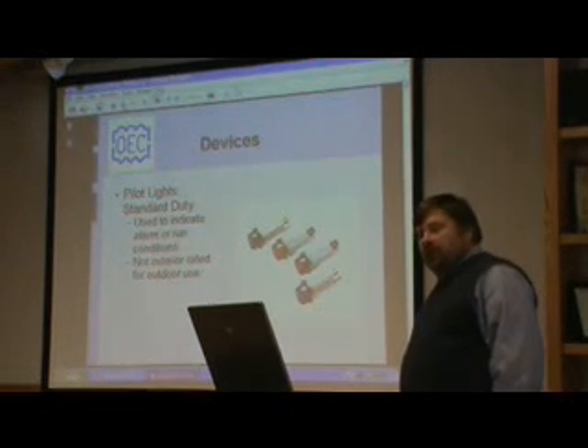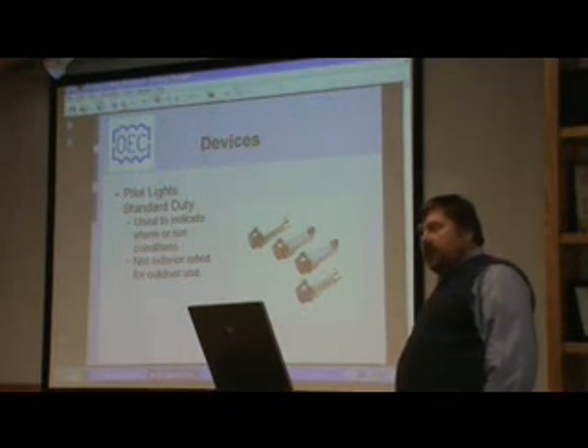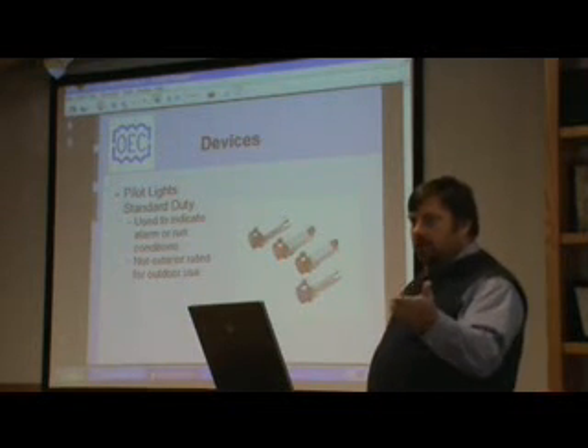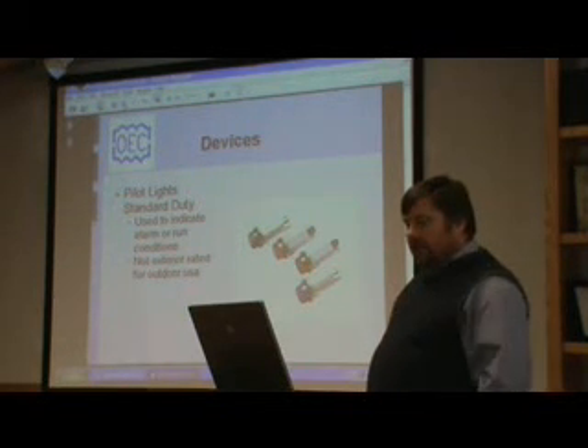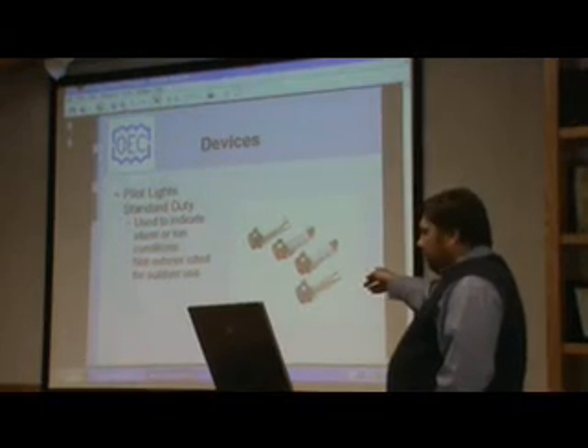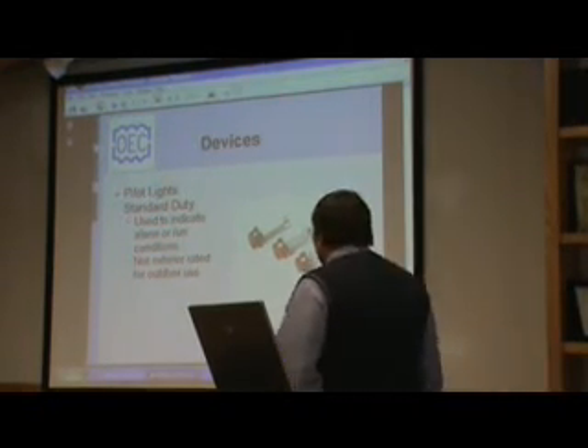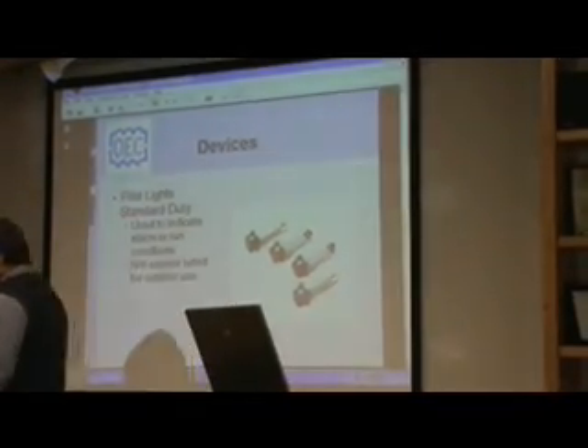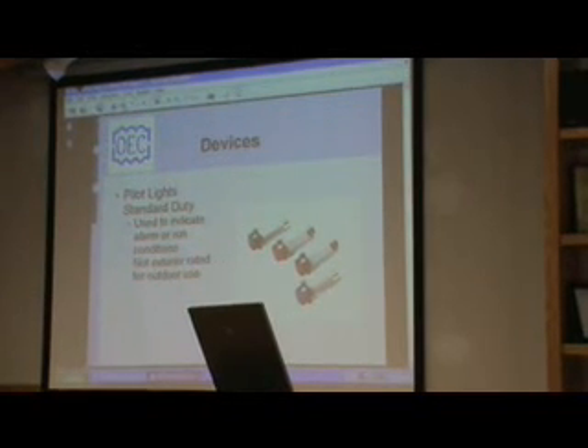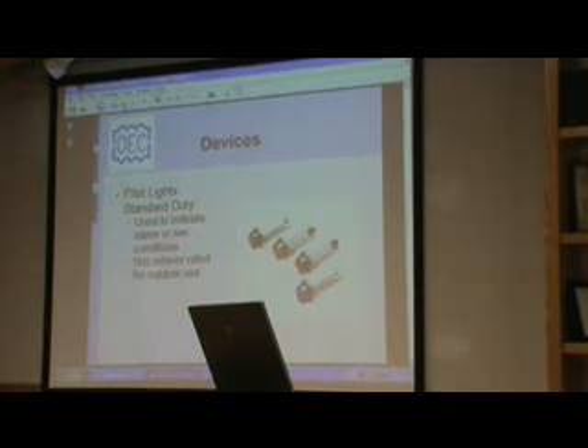Pilot lights are used in the panels to indicate some conditions happen. You have a seal fail or your pump's running high level or something like that. The device I showed here is the little neon light that we use in our panels. And the thing to know about this little neon light is it's not rated to stick on the outer door of the enclosure because it's not a sealed device. So if you stuck that out there and water could get into the panel possibly. So you usually see those mostly on the insides of the panel.